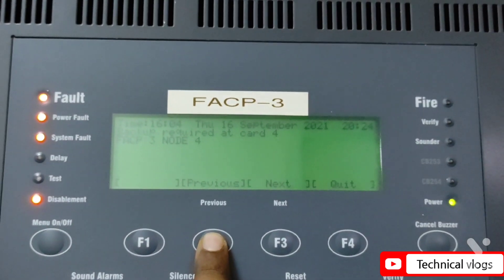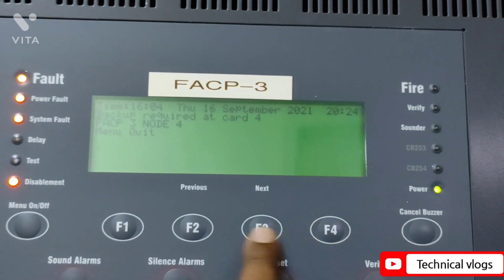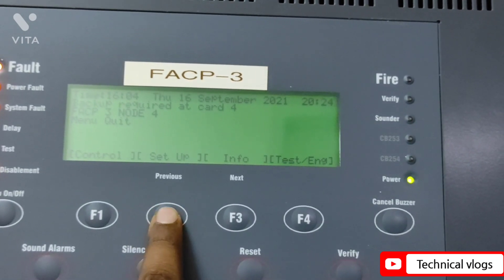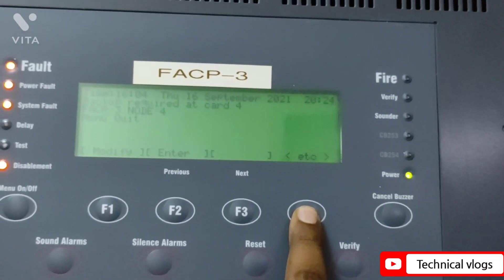If a backup is required for any loop, here is how to back up a loop card. Press Menu, go to Setup, then go to ETC. After that, go to Protect, then go to NVM Card, and then go to Disable.